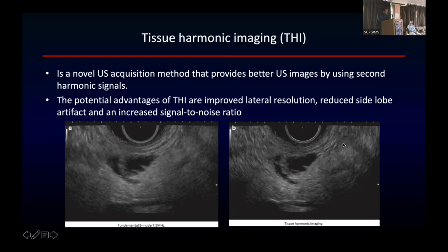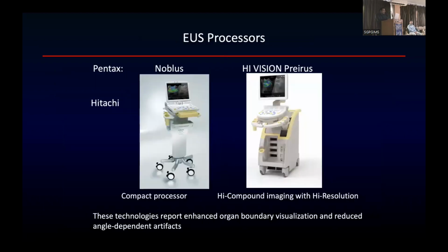And what is the advantage? You have improved lateral resolution, reduced side lobe artifacts, and increased signal to noise ratio. So if you see this first image and the second image, the resolution of this lesion is better visualized. It is just a press of a button. You switch on the button and you have THI imaging. There is another thing known as compound imaging, and the purpose of all these modalities is primarily to make your image better. For THI, it is improved lateral resolution, reduced side lobe artifacts, and increased signal to noise ratio. This is what THI is.